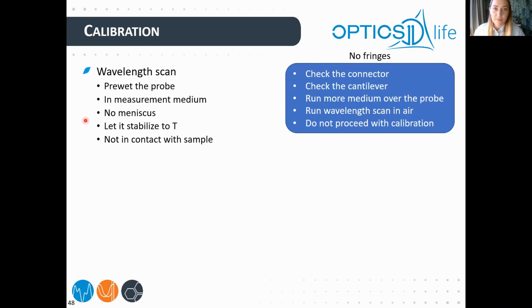So the wavelength scan, the first thing: we do need to pre-wet the probe. That's important. Then we need to do the wavelength scan in the measurement medium. Then we need to make sure that there's no meniscus. If you only submerge the probe at 500 nanometers, there will be a little pile up from capillary forces, we call it meniscus, and that might induce force on the cantilever. The cantilever needs to be in a completely neutral position without any forces on it during the wavelength scan. So yes, submerge the probe deeper into the medium so that it's stable.